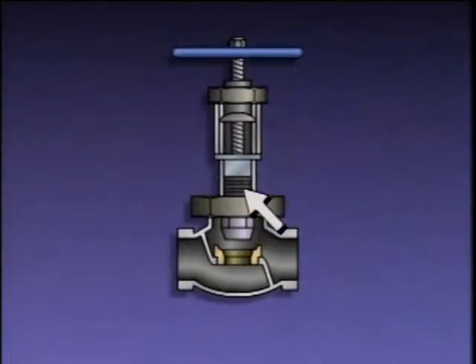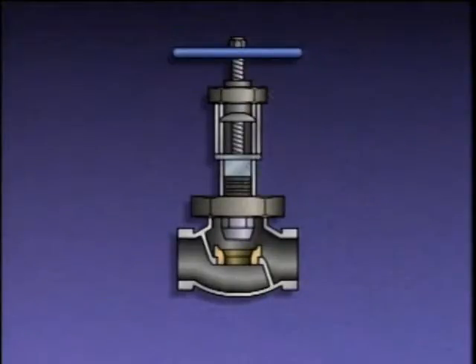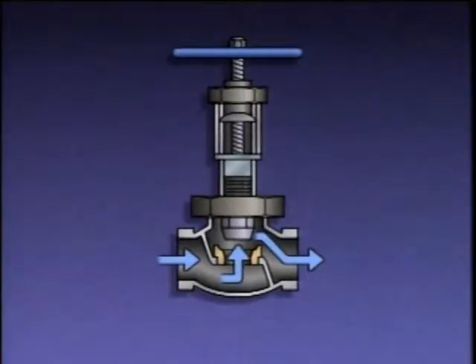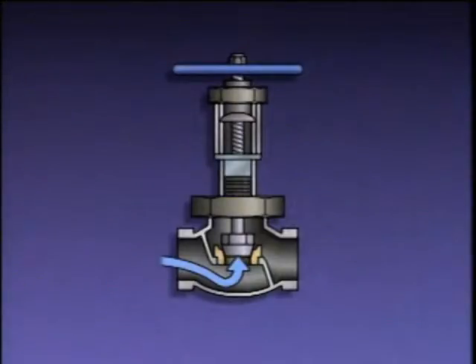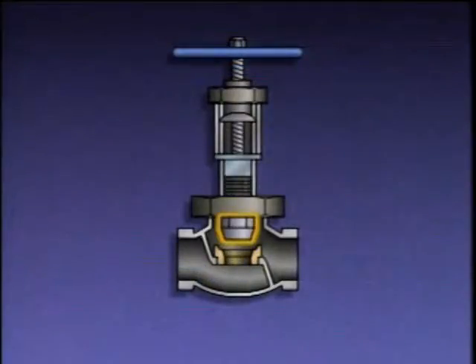A globe valve also has a stuffing box, packing, and a packing gland with a gland nut. Fluid flow enters a globe valve at one port and exits at another, making several right-angled turns as it passes through. Globe valves are normally arranged so that the higher-pressure side of the piping system acts under the disc, making it easier for an operator to open the valve. As a globe valve is opened, the entire disc and seat are exposed to fluid flow.